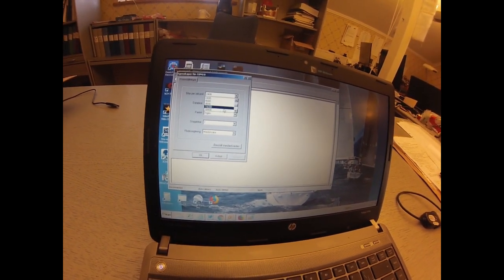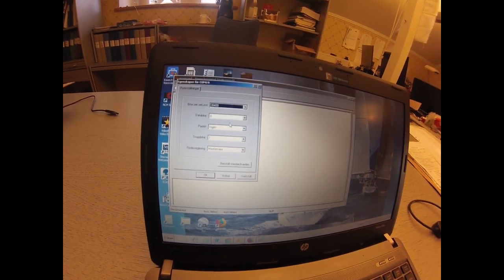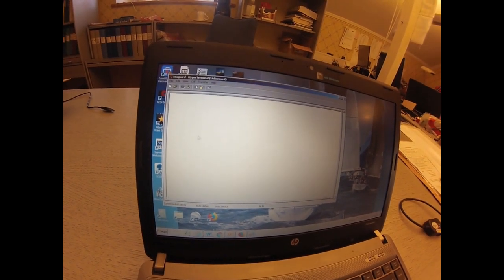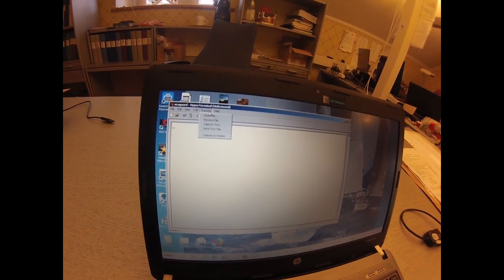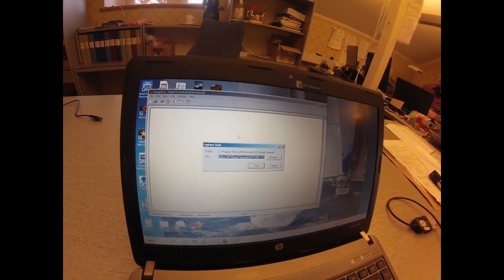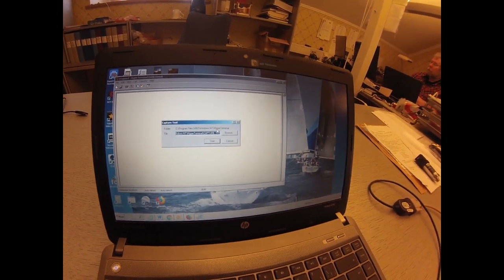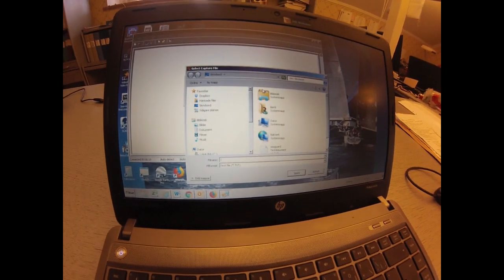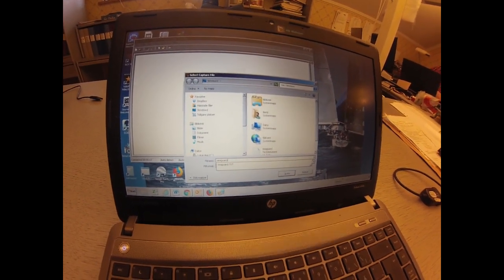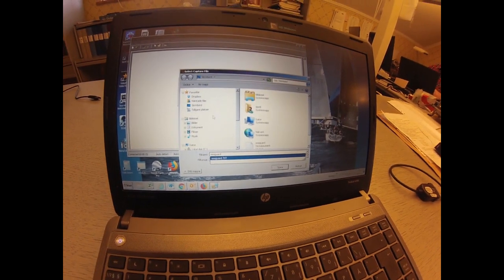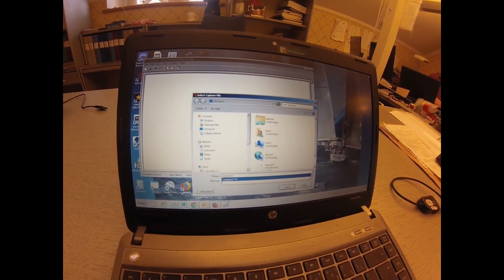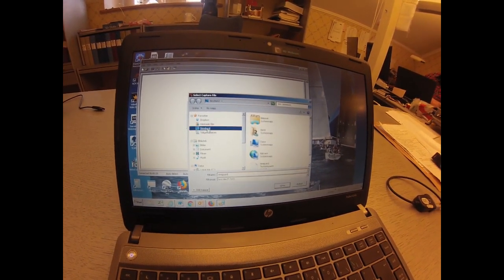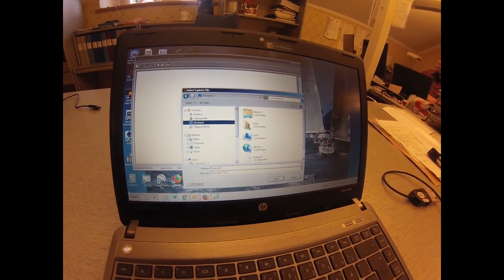Next you go to the baud rate, which is 38,400, and OK. Open transfer, capture text, and there will be a proposal where to save this text file. Click browse, name it Seaguard, and choose, for instance, desktop. Desktop and save.